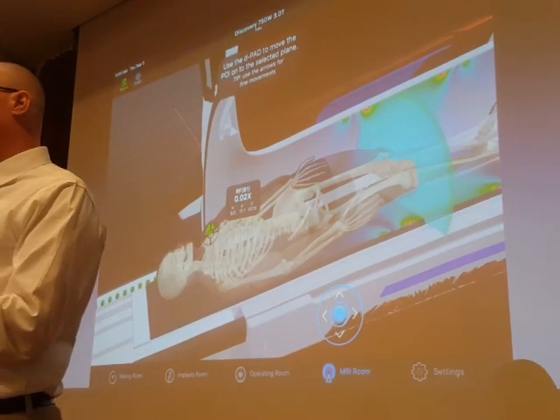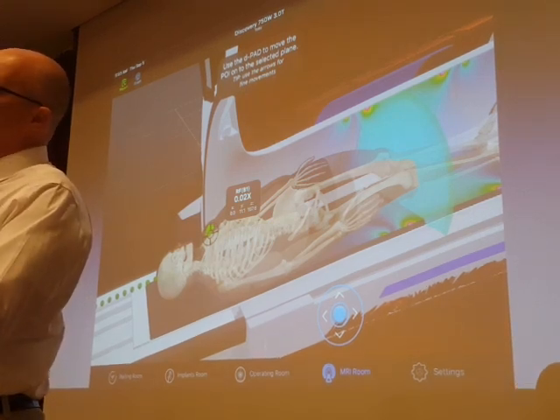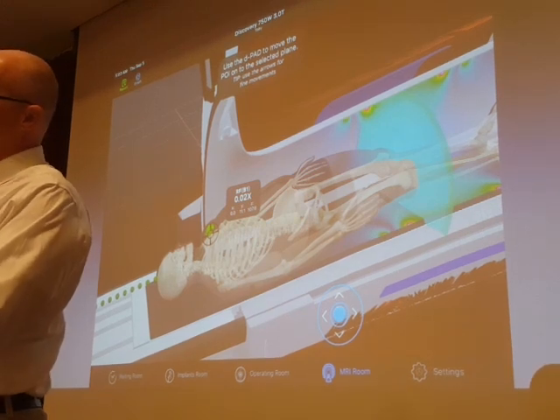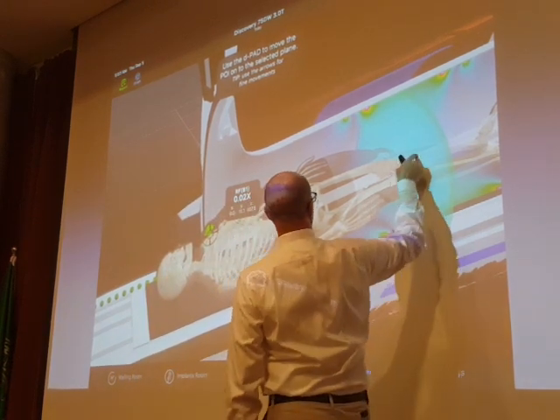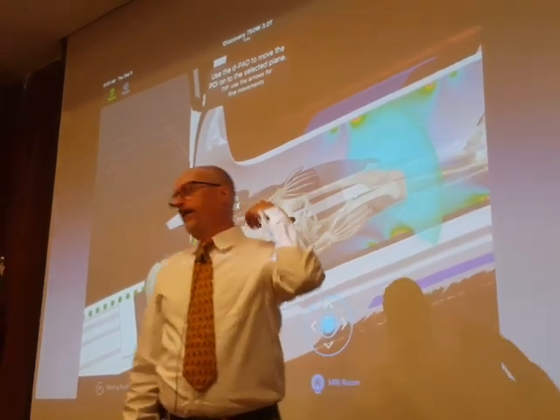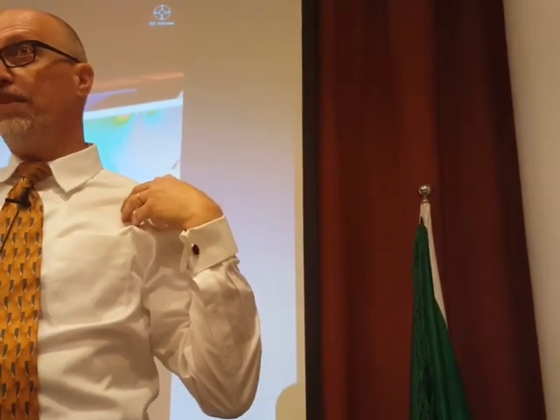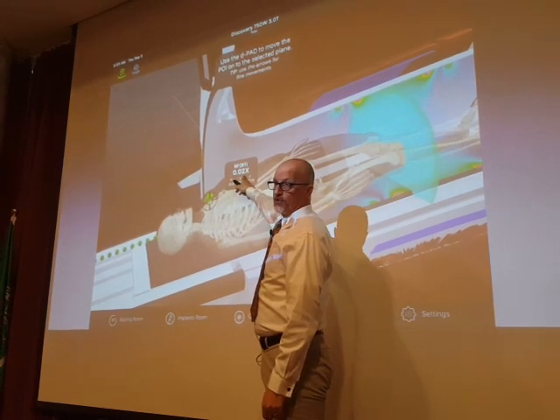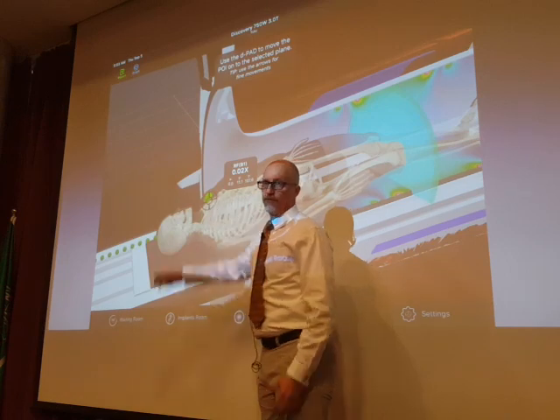For ultra-short bores like the Siemens Espree, because those systems are so much shorter, the RF coil is actually closer to the mouth of the bore. So whereas near the mouth of the bore here we're at about 2% of whatever the exposure is in the middle, for the Esprit — and Siemens hasn't modeled these systems, so this is speculation — I would expect it's maybe 10%, or 0.1 instead of 0.02 for the ultra-short bore.